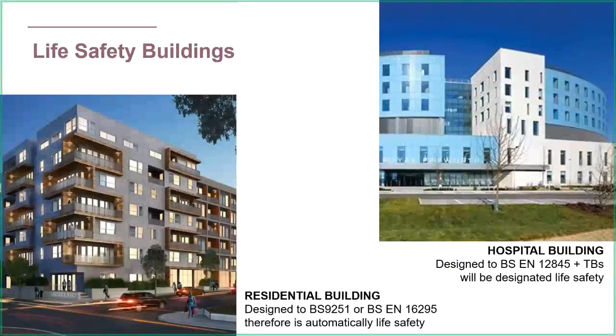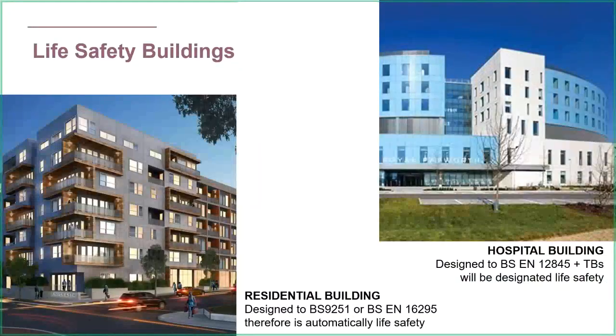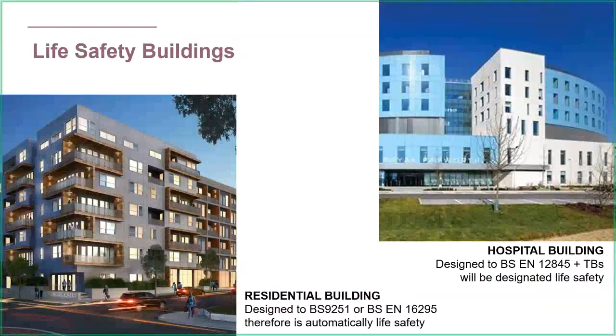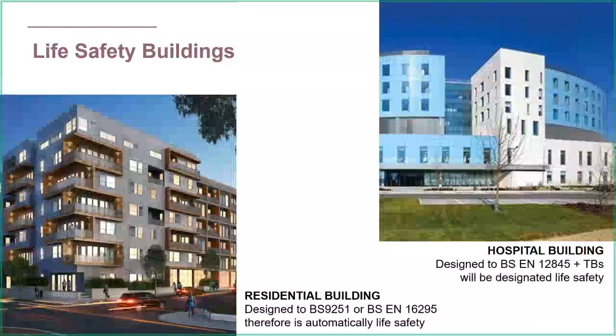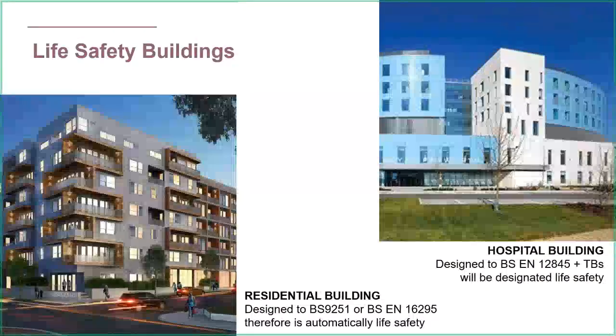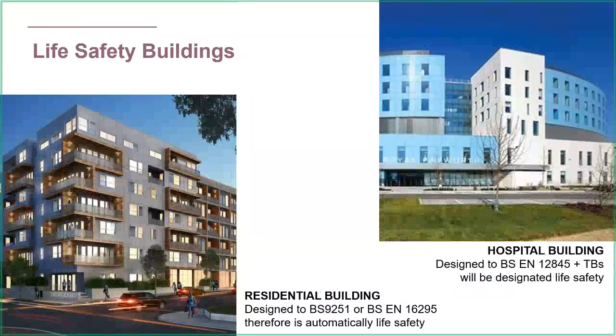In terms of what actually happens it's very similar - sprinkler heads will be heat activated, water will be discharged, alarms will sound. But for life safety, what we're actually trying to achieve is safe evacuation from the building - keeping exits clear, keeping smoke to a minimum, suppressing the fire to give people extra time to evacuate. Also, who's in charge differs: for property protection it's the insurance company, but for life safety it's the building owner and other stakeholders - for example, NHS trusts for a hospital.